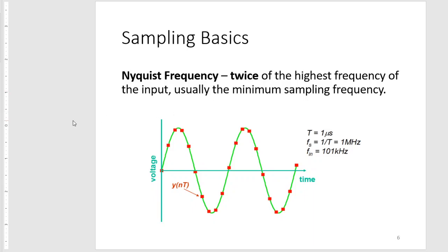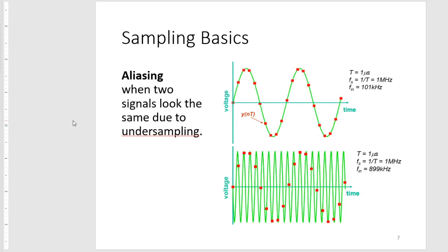To make more sense of this is the term aliasing. Aliasing is when two signals look the same due to undersampling or sampling under the Nyquist frequency. Here at the top is the 101 kilohertz signal, and here at the bottom is an 899 kilohertz signal. If we just sample at one megahertz, we can get exactly the same points from a 101 kilohertz signal.